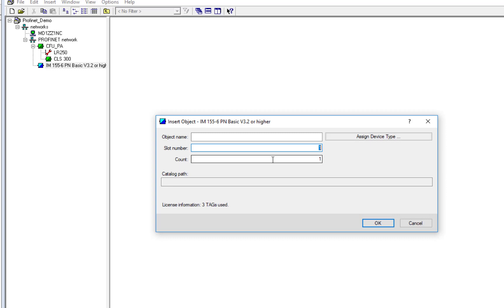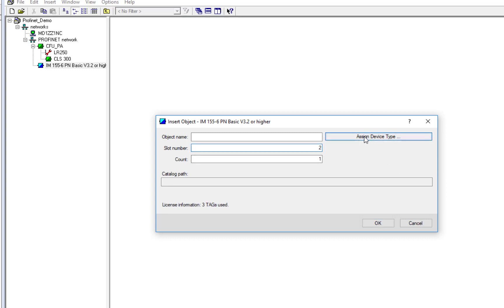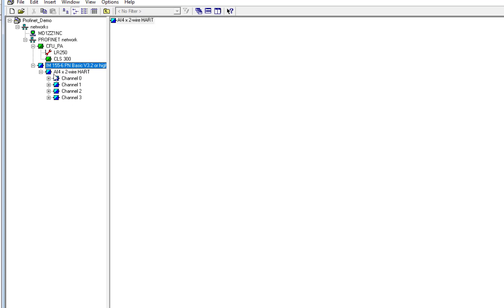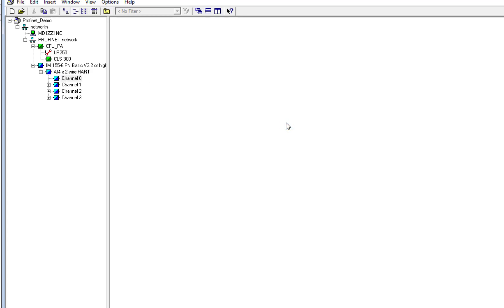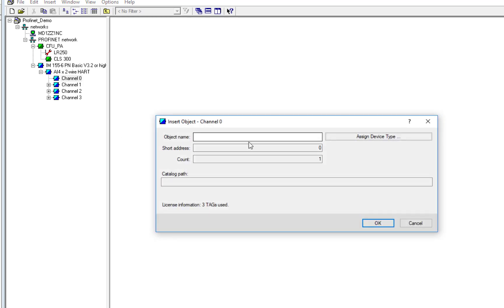So we know it's the second slot that's going to be HART, and then it's a HART input module. So at this stage, we have four channels. Now, you may not have a HART instrument on all of these channels, but PDM will still bring back the diagnostics, if it's a wire break or whatever, but we actually have a device connected to channel 0. So we'll insert a new object there. And the HART address is always 0. I can't edit that. So if somebody's changed your HART address on the instrument, they've actually put it into multi-drop mode, and it won't communicate to the Siemens HART input cards. So we need to be set to 0.